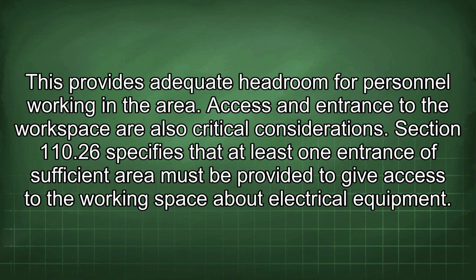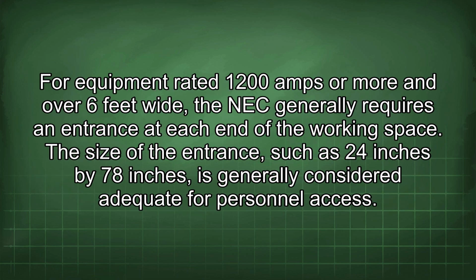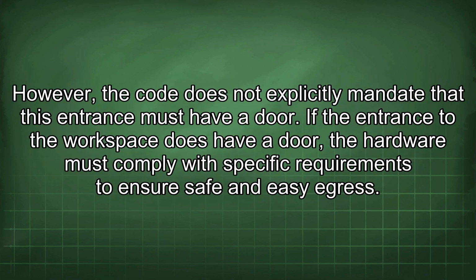Access and entrance to the workspace are also critical considerations. Section 110.26 specifies that at least one entrance of sufficient area must be provided to give access to the working space about electrical equipment. For equipment rated 1200 amps or more and over 6 feet wide, the NEC generally requires an entrance at each end of the working space. The size of the entrance, such as 24 inches by 78 inches, is generally considered adequate for personnel access. However, the code does not explicitly mandate that this entrance must have a door.